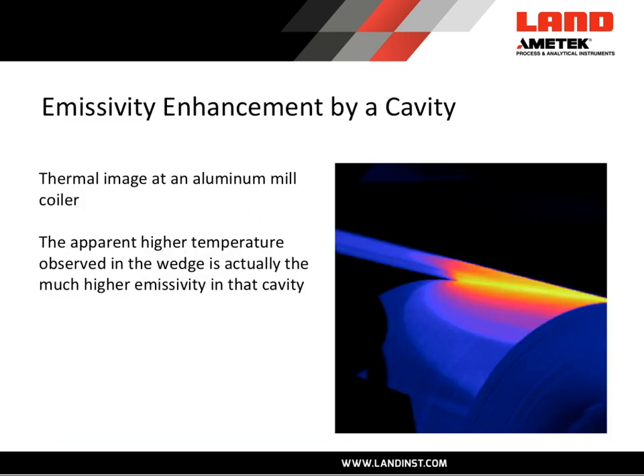In this thermal image of a down coiler in an aluminium rolling plant, we see the strip coming towards the coil and being coiled up at the end of the line. This thermal image shows the thermal radiation emitted from that coil and the strip. The very bright yellow line is the enhancement of emissivity in that wedge area. It's not that the temperature is higher there — it's that the aluminum, which has an emissivity of 0.13, has an emissivity close to one in that cavity, making it a much easier measurement compared with looking at the open strip.